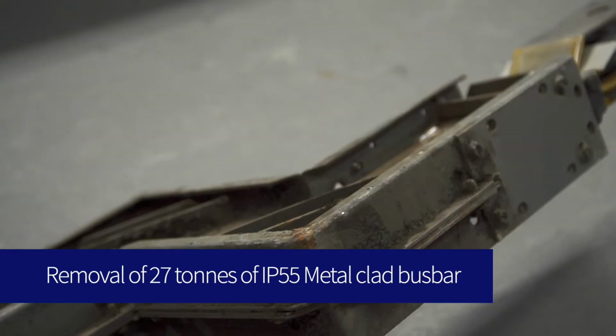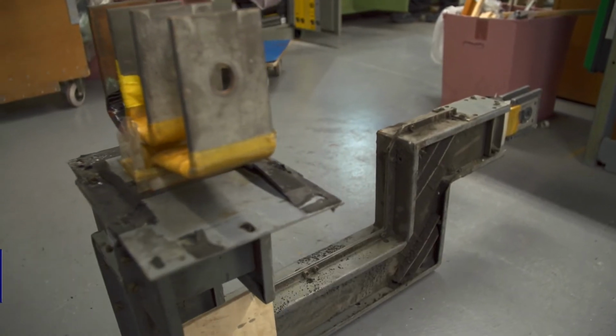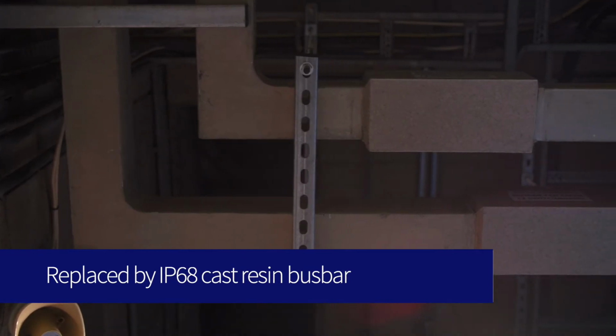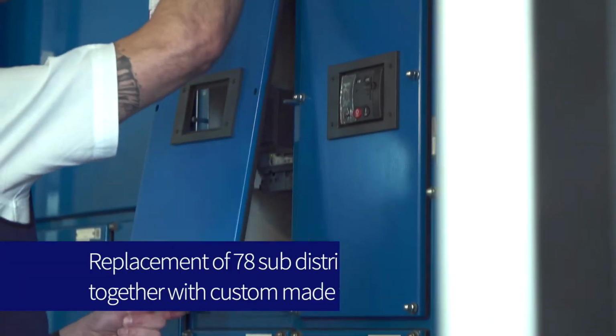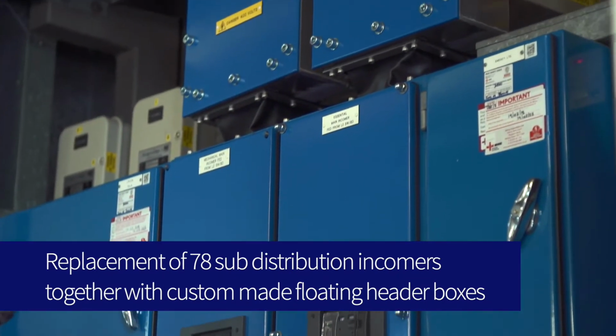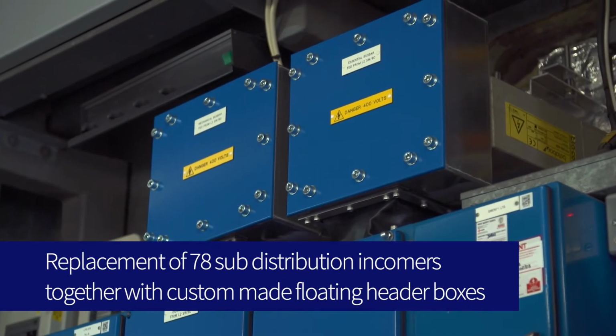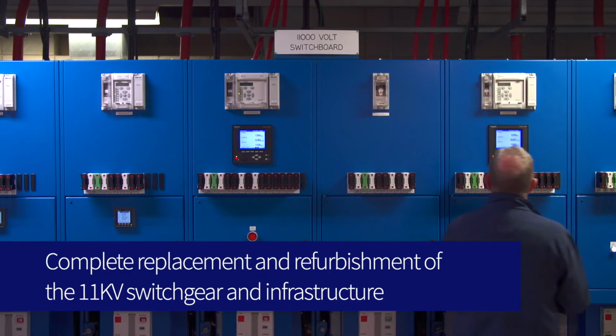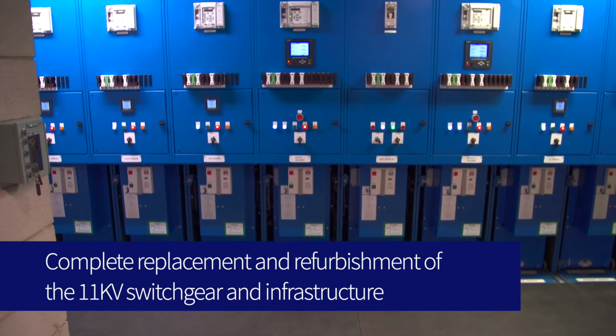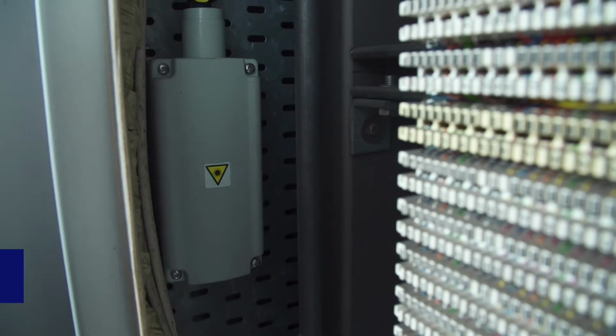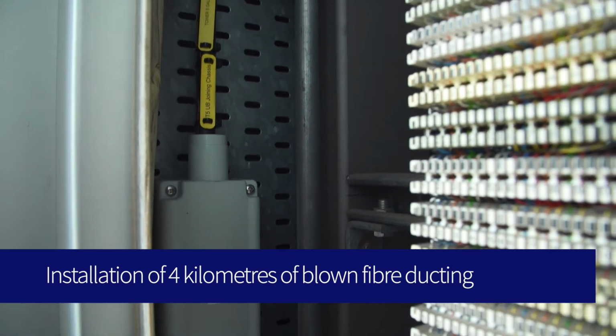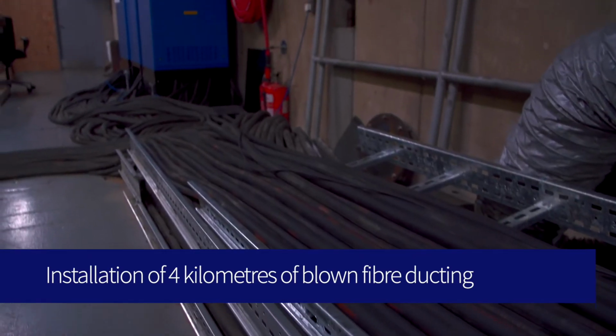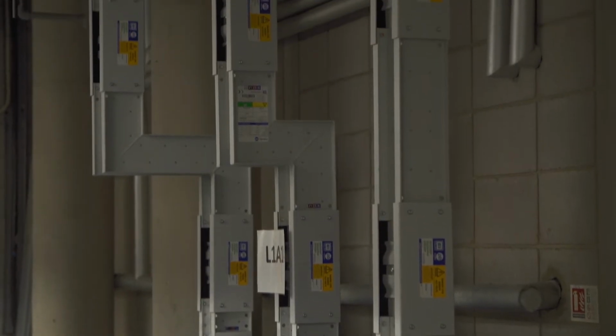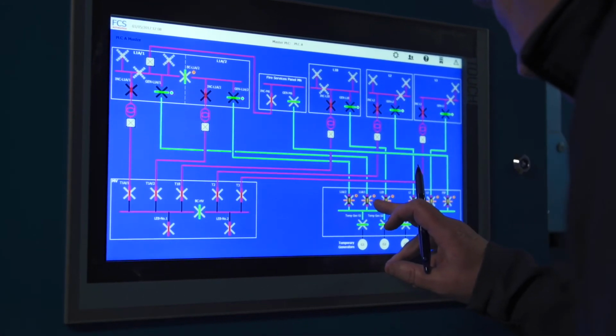The project included the removal of 27 tons of IP55 metal-clad busbar, replaced by IP68 cast resin busbar, the replacement of 78 sub-distribution incomers together with custom-made floating header boxes, complete replacement and refurbishment of the 11 kilovolt switchgear and infrastructure, installation of 4 kilometers of blown fiber ducting and cabling serving the newly installed energy monitoring system, and vendor-agnostic network automation system monitoring the medium voltage, low voltage, and in-house power generation.